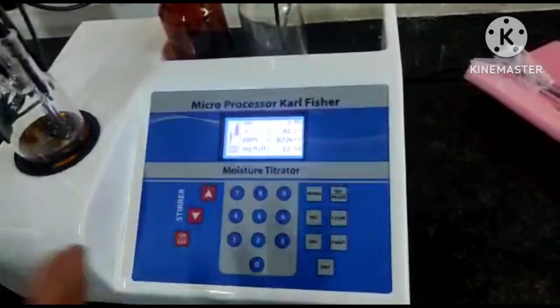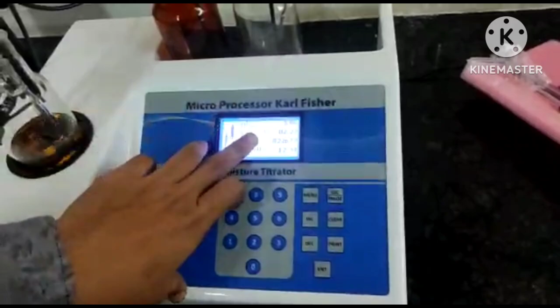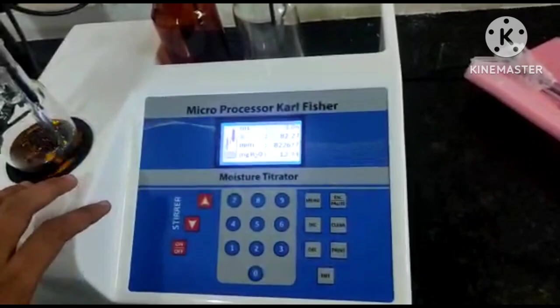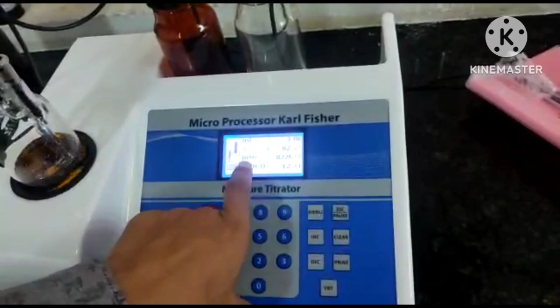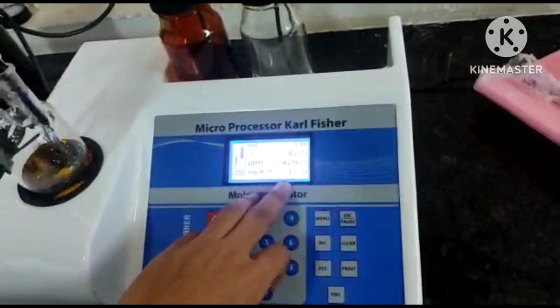Once your sample is neutralized, it means extracted, then the machine will give you the values, the actual amount that is consumed by your sample, the amount of reagent that has been consumed, percentage of moisture inside your sample, ppm value of moisture, and mg water content. So these 4 values the machine will give you. After that, you have to press enter.